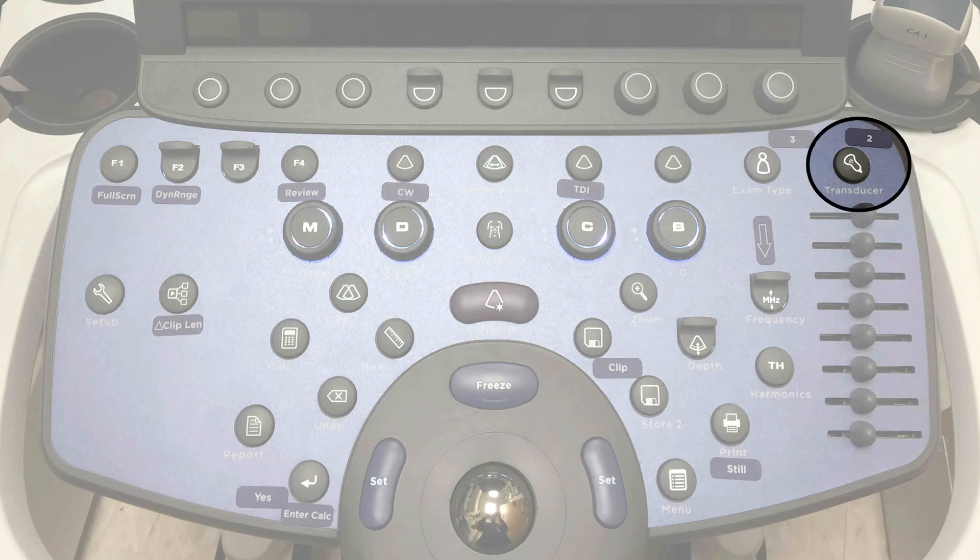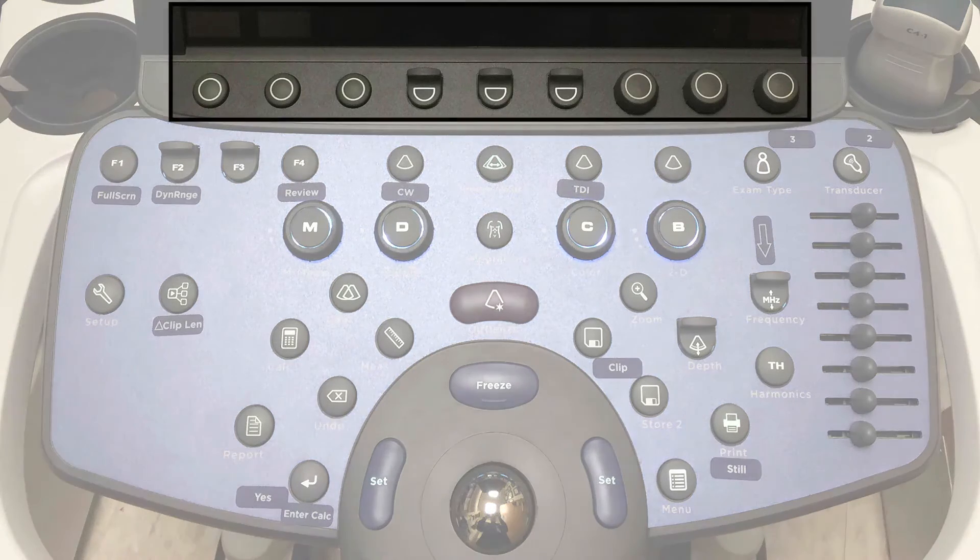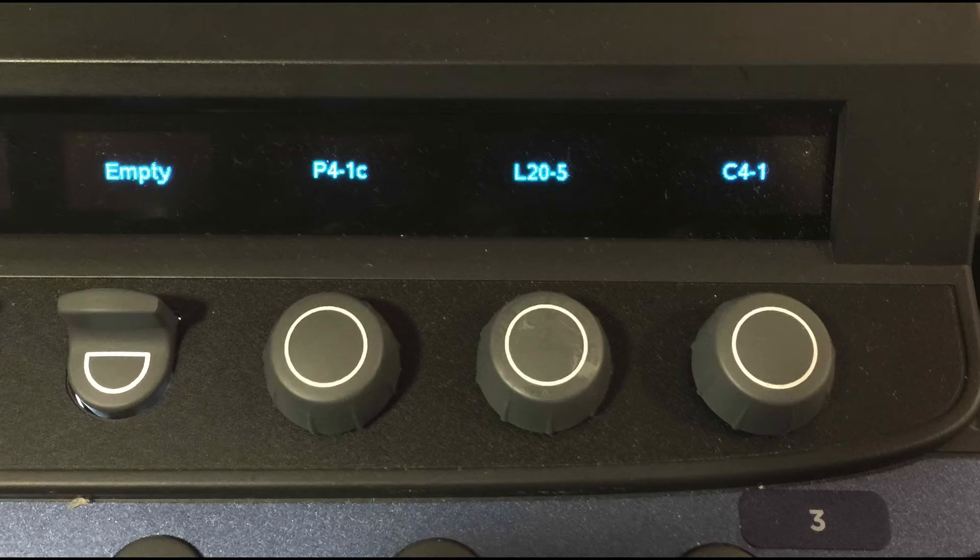you're going to press the transducer button — that's number two. This will allow you to select a transducer, and then you're going to go to the soft keys. The first three dials will list the three probes that are connected: in this case the phased 4-1, the linear 20-5, and the curved 4-1.